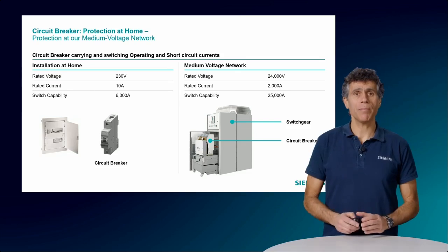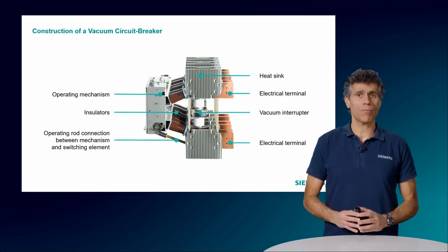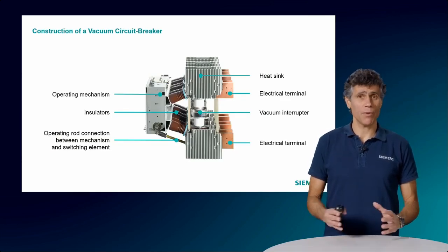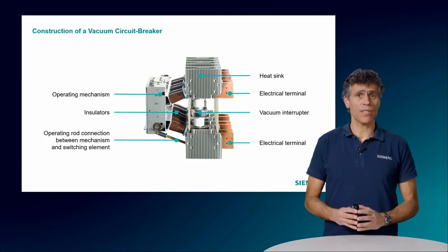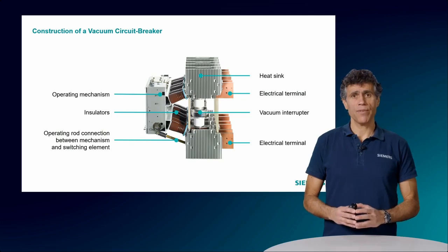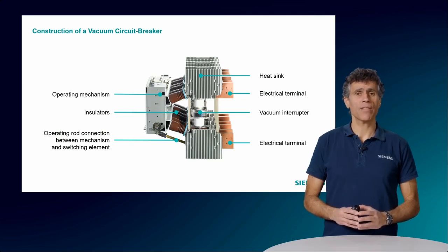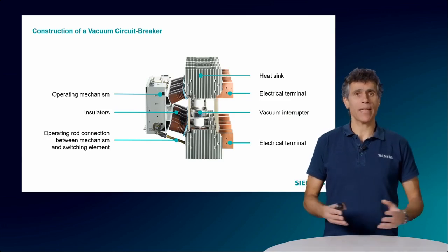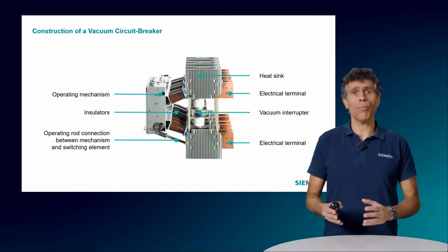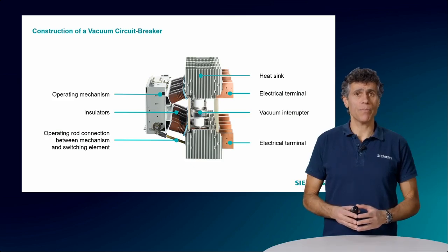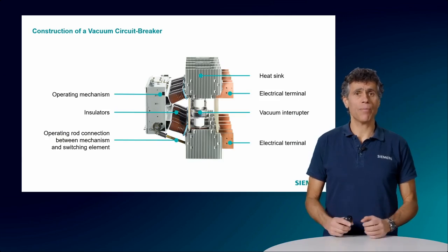Let's move a bit deeper and see how a vacuum circuit breaker, which is by far the most commonly used type of breaker nowadays, is built. Despite several designs from different manufacturers, the basic functions and components are usually consistent. They all have an operating mechanism. This is crucial for open and close operations of the breaker.